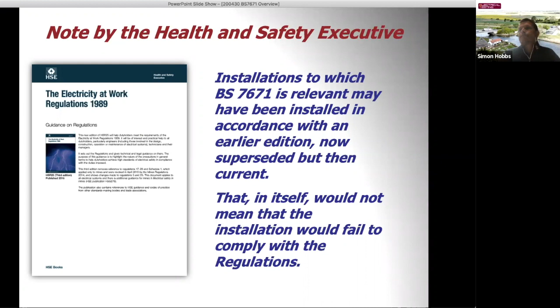So let's have an overview of BS 7671. It's in 7 parts. Part 1 is scope, object, fundamental principles. Part 2 is definitions. Part 3 is assessment of general characteristics. Part 4 is protection for safety. Part 5 is selection and erection of equipment. Part 6 is inspection and testing. And finally part 7 is special installations or locations. There also comes with the document large appendices that support the main parts of the regulations, and we'll look at that as we move through, particularly into parts 4 and 5.